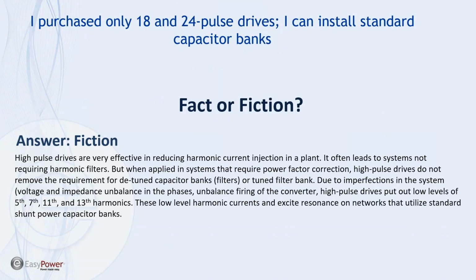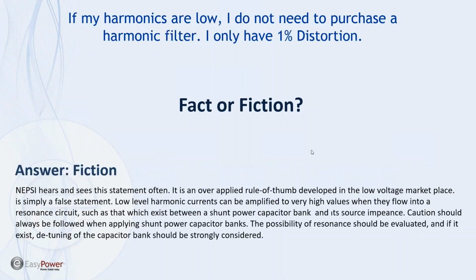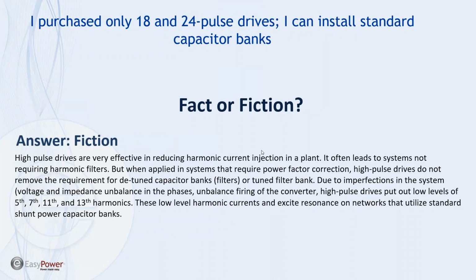So when you don't have these perfectly balanced conditions, a small amount of 5th, 7th, 11th, 13th harmonic currents will be put out. Those small amounts of current can resonate with capacitors in the system and can result in problems. So again, it falls back to the previous question: if my distortion is low, do I need to consider filters? Yes. If you're going to install capacitor banks, they most likely will still need to be installed as a filter or as a detuned capacitor, but certainly not as a capacitor bank by itself without a tuning reactor.